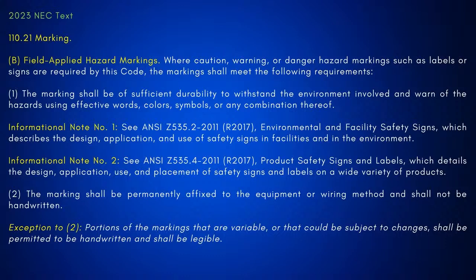You can use any type of label that gives a warning, has the specific information that's required, and is permanently affixed. This is really funny, we might even do another myth about this coming up, but I actually found this out. You are able to use a label maker because the label maker tape is suitable for the environment. It says right on it that it's suitable to be used in that environment. One of the companies I did work for had bought a system that made the labels. I forget which brand it was, but the label itself was suitable for the environment, and they were able to give the warning up top and then the information below when they put it on all their equipment. And that was perfectly fine.